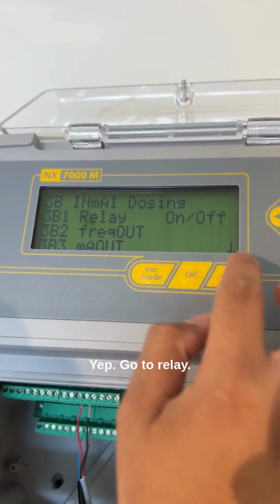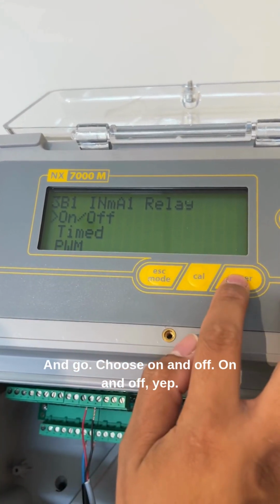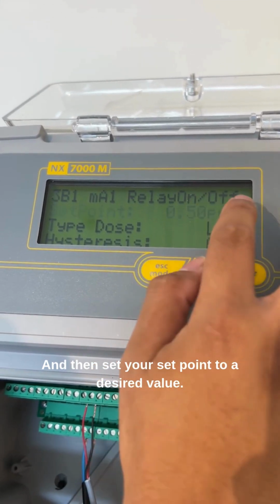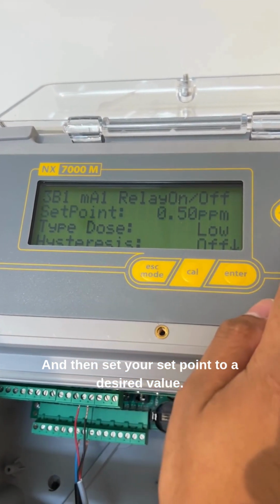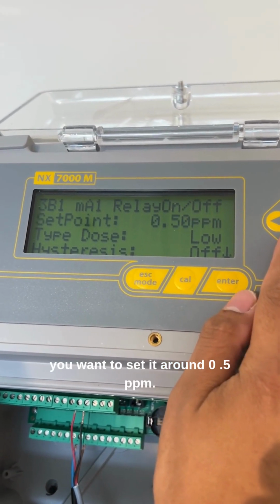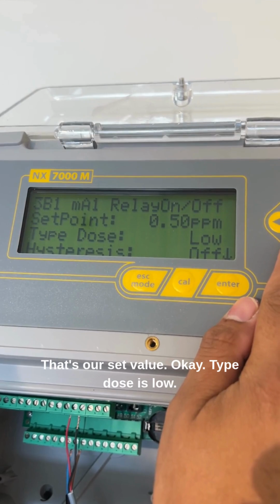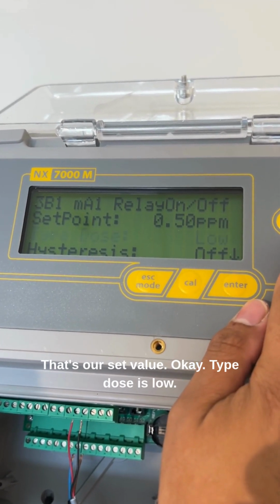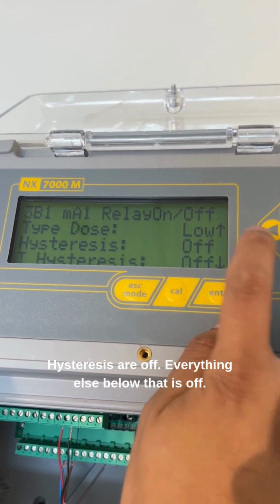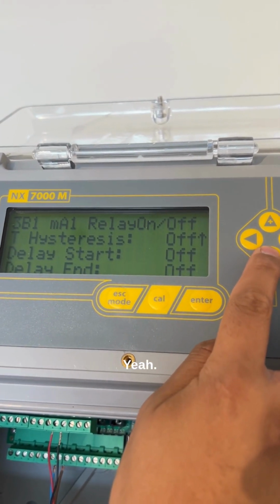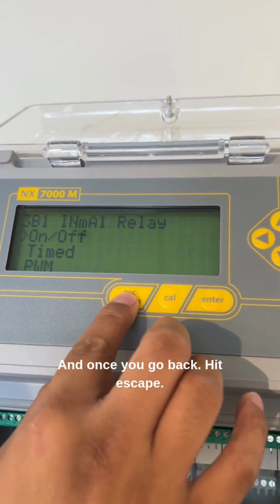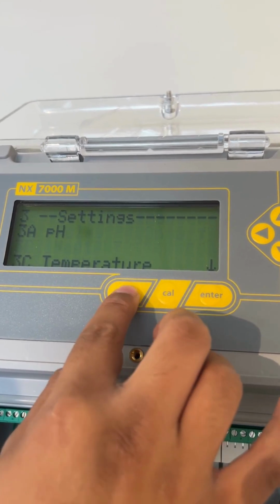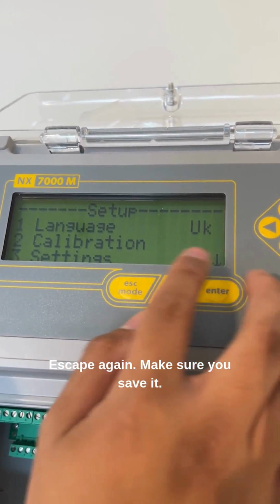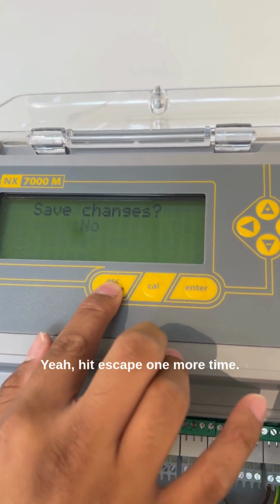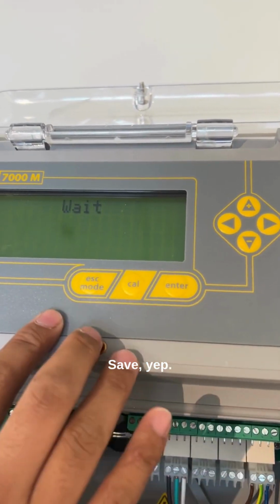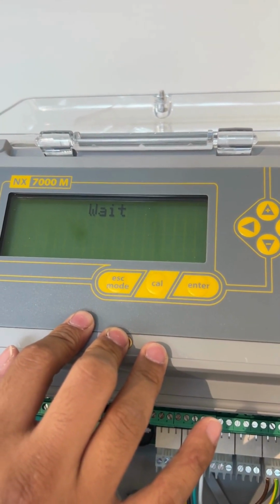Yep. Go to relay. Choose on and off. Yep. And then set your set point to a desired value. So in this case, you want to set it around 0.5 ppm. That's our set value. Okay. Yeah. Type dose is low. Hysteresis are off. Everything else below that is off. Yeah. And once you go back, hit escape. Escape again. Make sure you save it. Yeah, hit escape one more time. Save. Yeah. There you go.